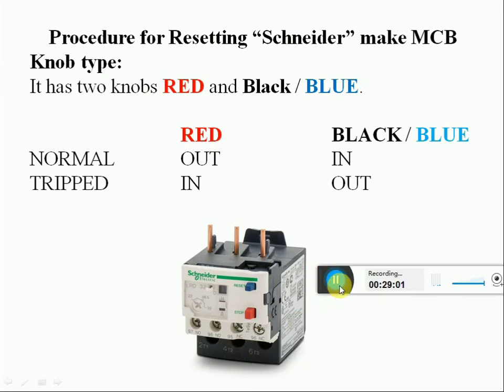You can see here 2 knobs are there, red and blue. If red knob is in out position, normal position is out. If blue knob or black or green knob in out position, MCB in tripped condition. If red knob is in out position, MCB working condition. If blue or black or green knob is in out position, MCB in tripped condition. If MCB trip, we have to press this blue, black or green knob for resetting of this type of MCB.